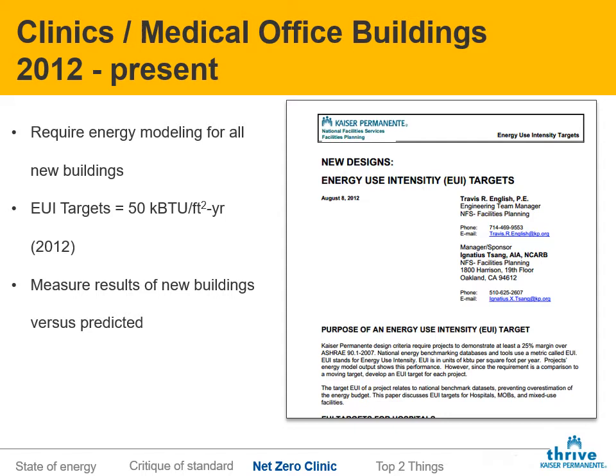So starting in 2011, 2012, we started an energy program on our medical office buildings. First things first, we require an energy model on every building. And then that energy model has to show the modeled performance of the building at an energy target. And on the West Coast, our energy target for medical office buildings was 50 EUI. Now that's the part that relates back to standard 170, because if you put 6 air changes in all your X-ray rooms and exam rooms and treatment rooms, you can't meet an energy target of 50 EUI.